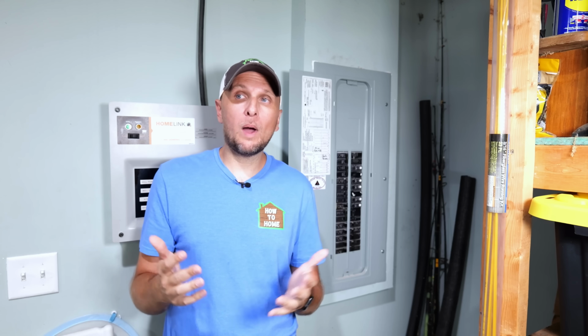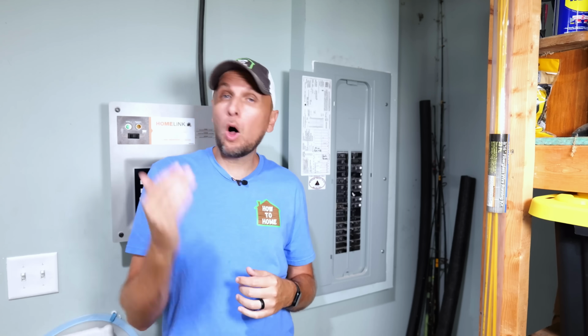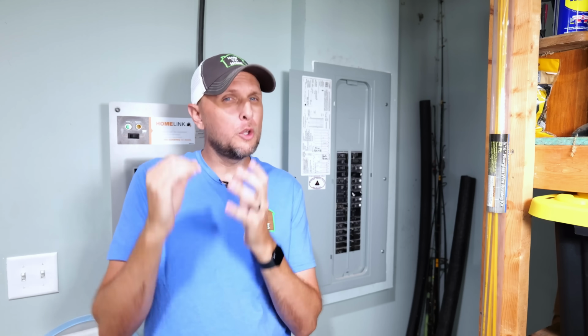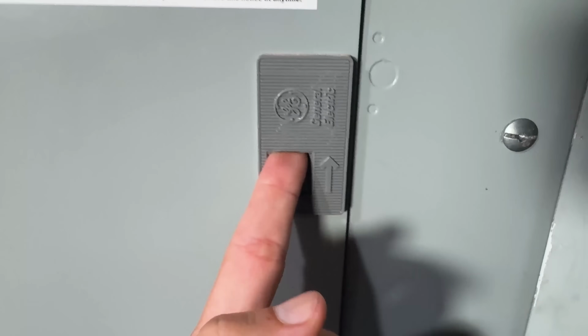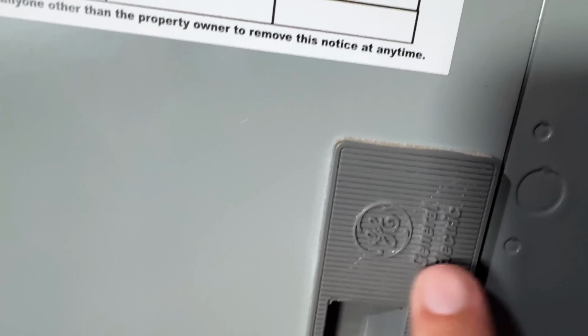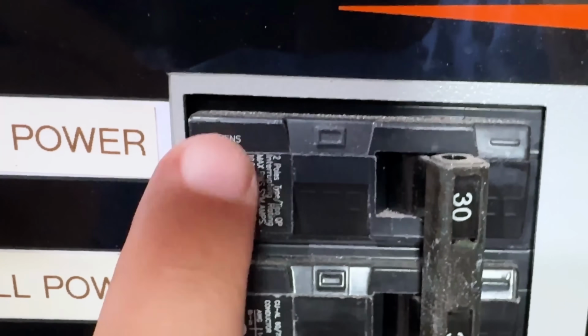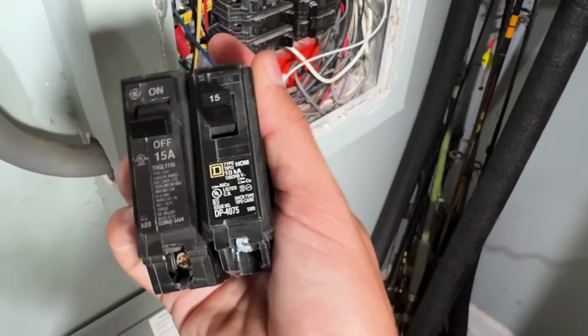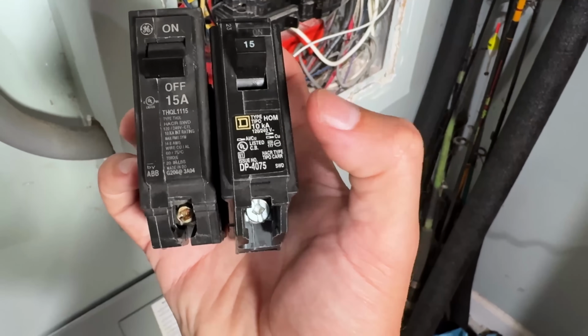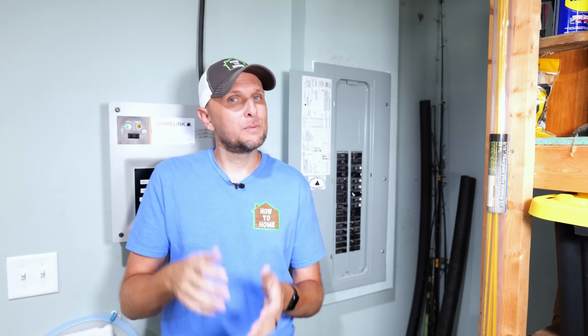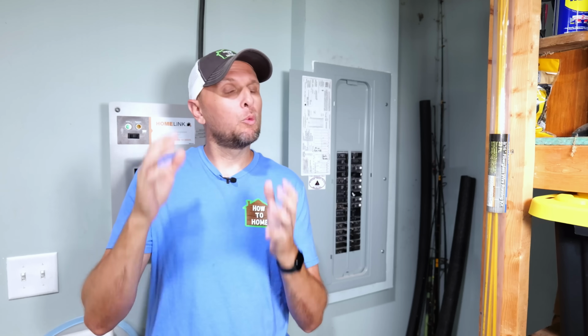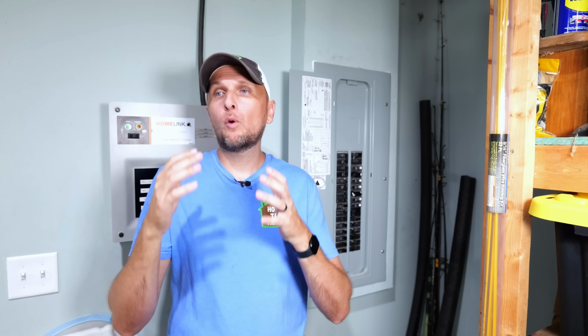So what is the fix for this? It's actually pretty easy: always use breakers that match your panel's brand. All you have to do is check the panel's label for the UL listed breakers. If it's a Siemens panel, get Siemens breakers. If it's a GE panel like this one, get GE breakers. An Eaton panel, Eaton breakers. You get the idea. It really is worth the extra cost to avoid a potential and very likely issue.